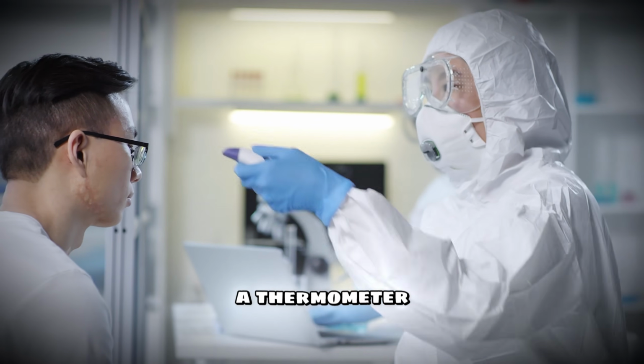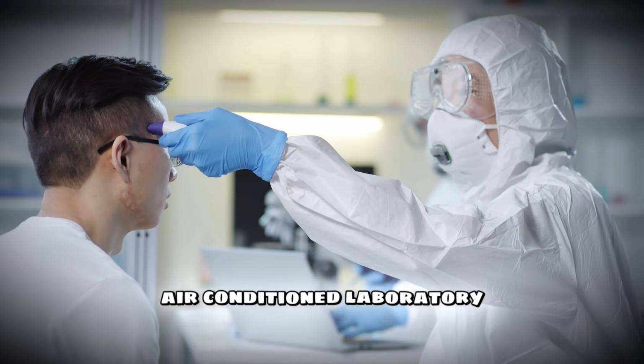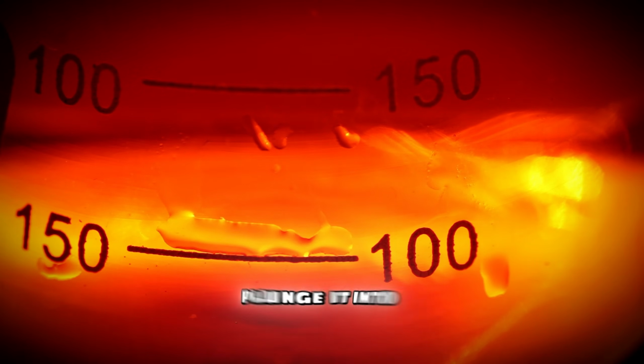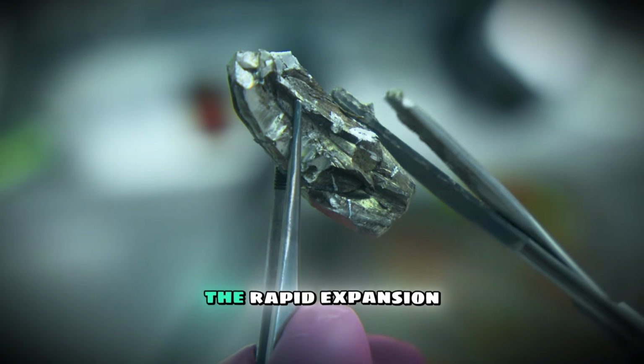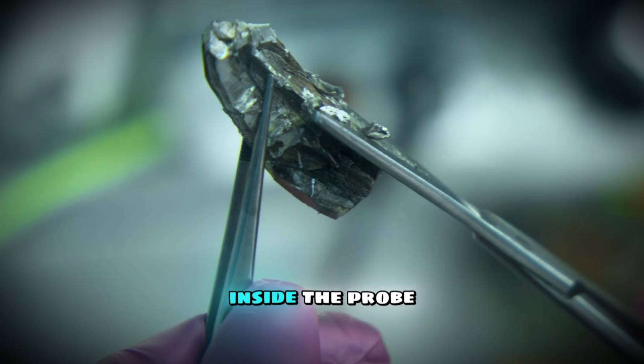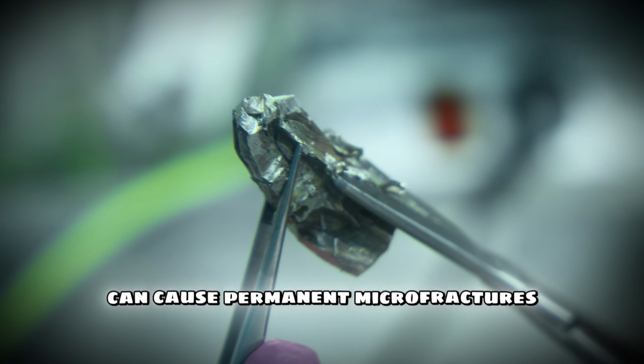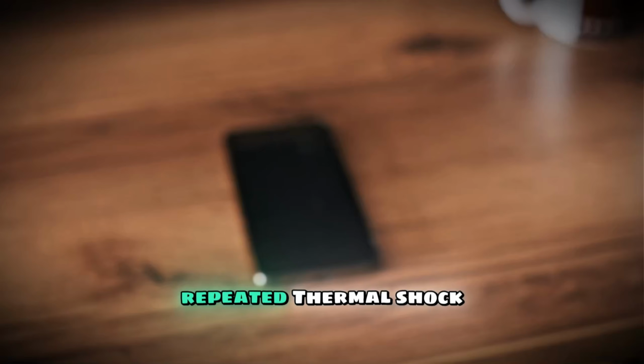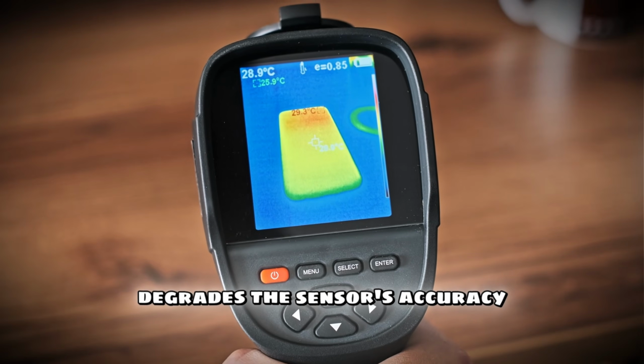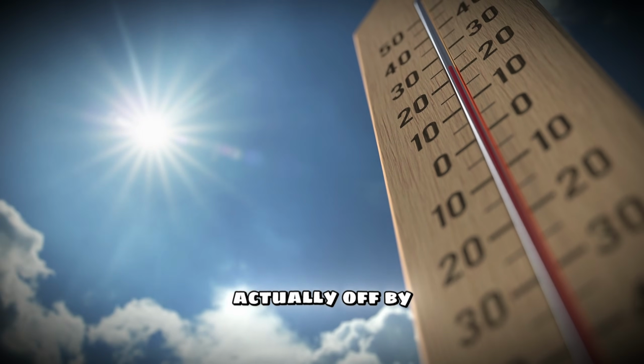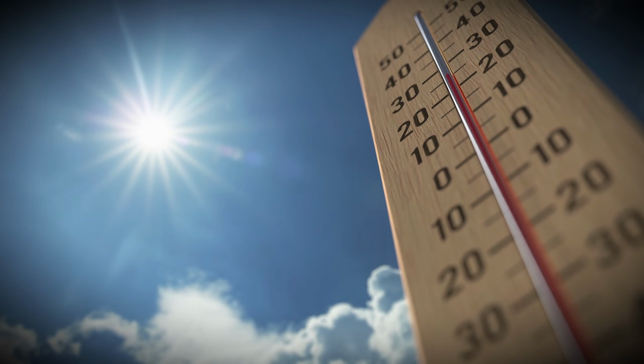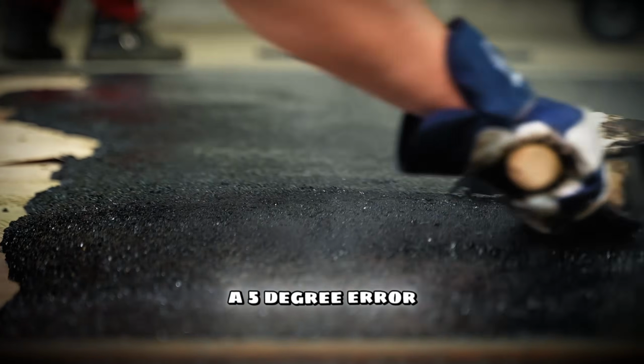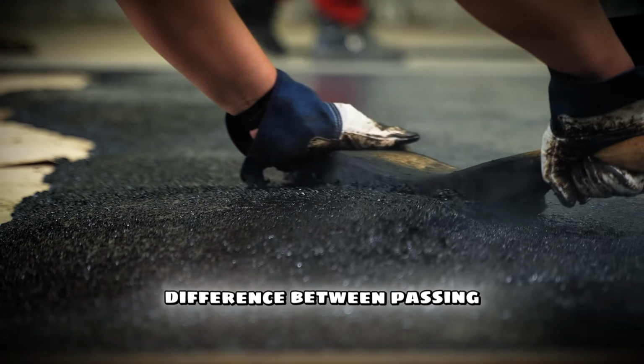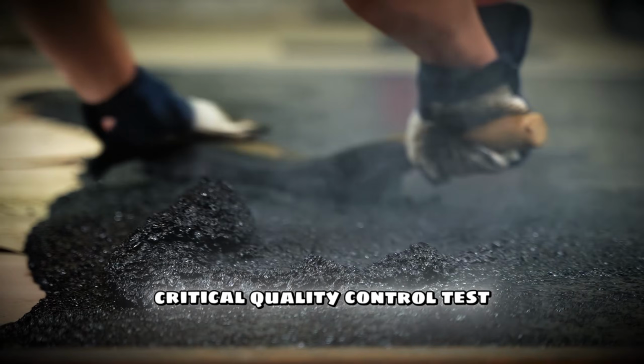Next is thermal shock. If you take a thermometer that has been sitting in an air-conditioned laboratory and immediately plunge it into a highly heated asphalt mix or a freezing liquid, the rapid expansion and contraction of the metals inside the probe can cause permanent microfractures. Over time, repeated thermal shock degrades the sensor's accuracy. You might think it is reading 200 degrees, but it is actually off by 5 or 10 degrees. In materials testing, a 5-degree error can mean the difference between passing and failing a critical quality control test.